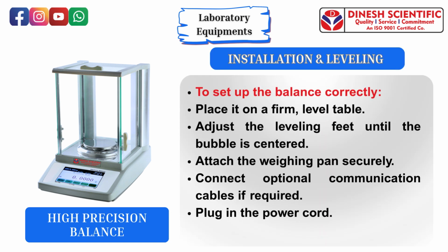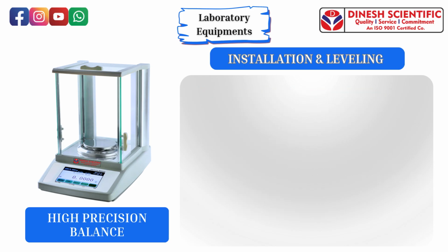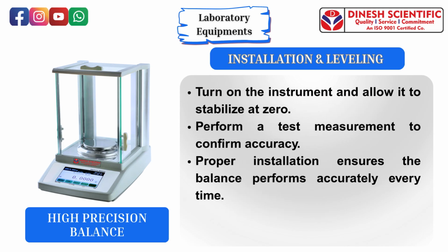Installation and leveling. To set up the balance correctly, place it on a firm, level table. Adjust the leveling feet until the bubble is centered. Attach the weighing pan securely. Connect optional communication cables if required. Plug in the power cord. Turn on the instrument and allow it to stabilize at 0. Perform a test measurement to confirm accuracy. Proper installation ensures the balance performs accurately every time.